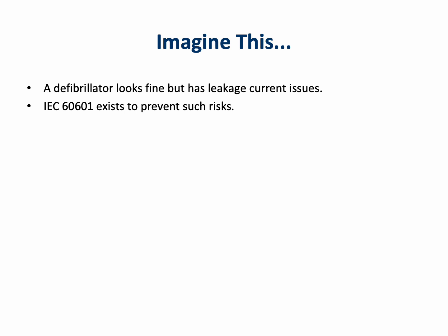So I just want you to imagine this. Imagine you're maintaining a defibrillator in a hospital, right? It looks fine from the outside, no cracks, nothing. But actually, internally, a leakage current issue could actually shock the patient if they touch it, if there's a live part of it. And essentially, standards like IEC 60601 exist to stop that from happening.